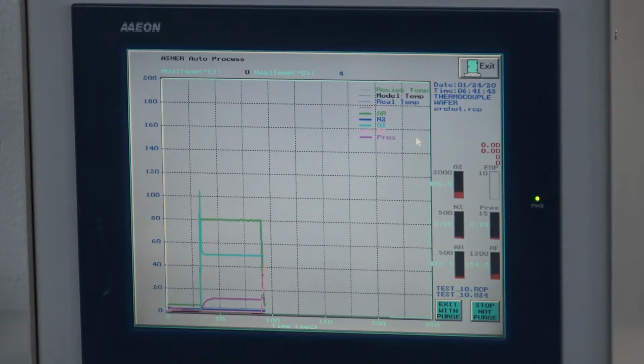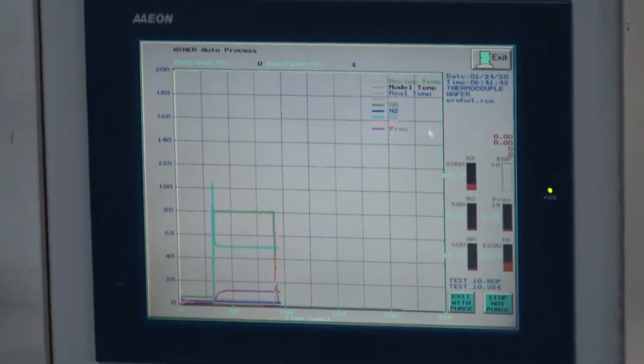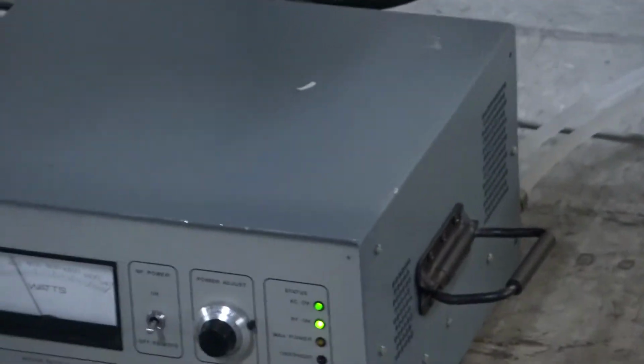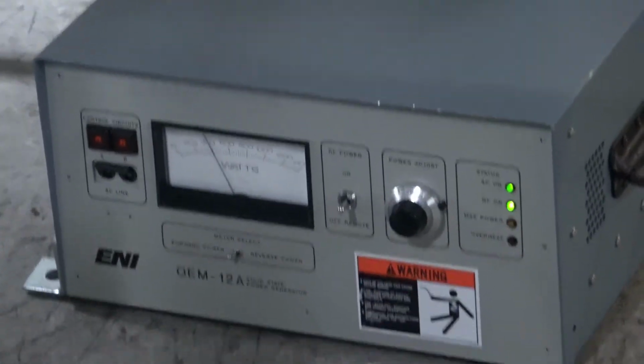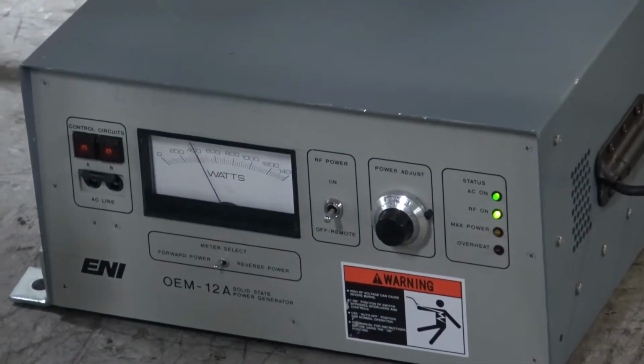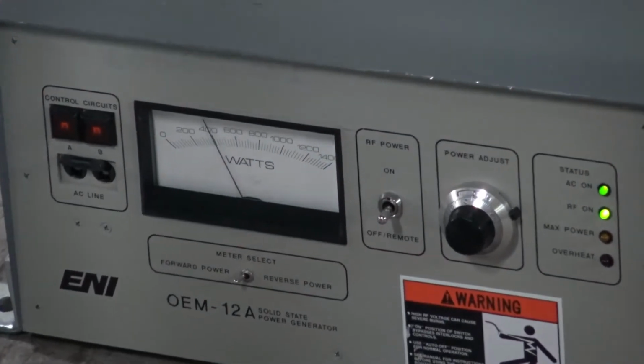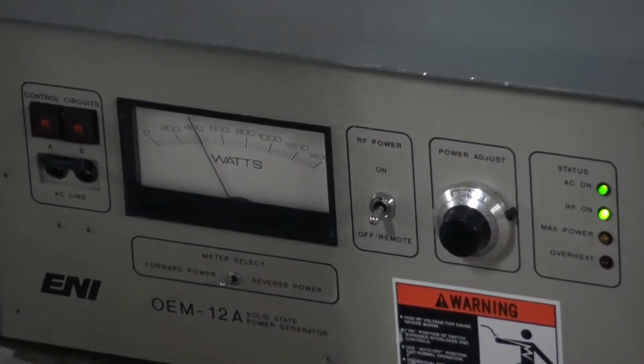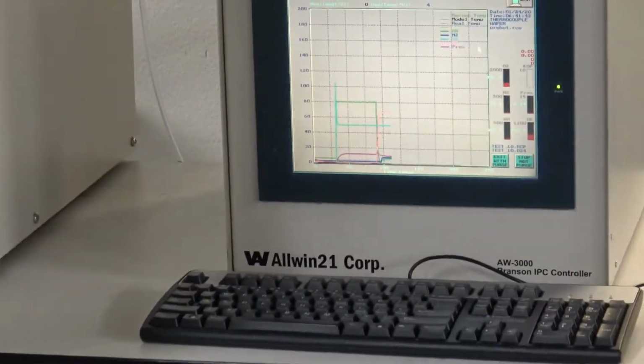Okay, the RF just came on. If you look over here, I want to point down to the RF generator. I have it set at 400 watts, and it's reading exactly 400 watts, so it's reading what it's supposed to. If you look at the screen, it's hard to see because of the colors, but it also says 400 watts.